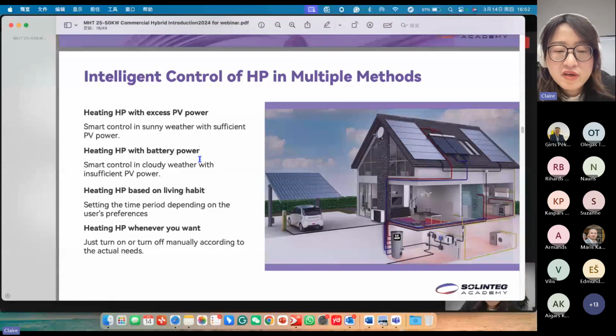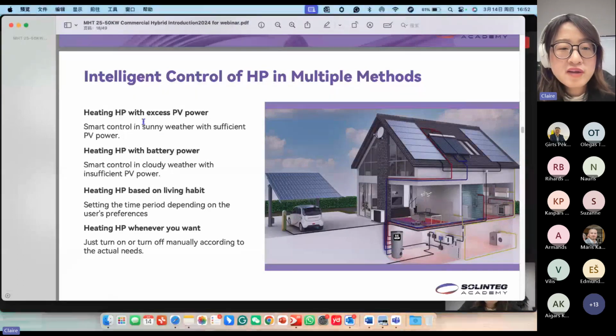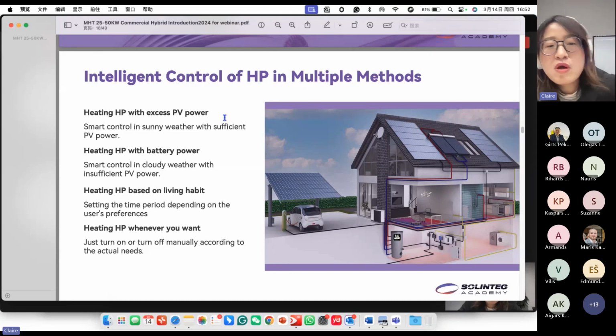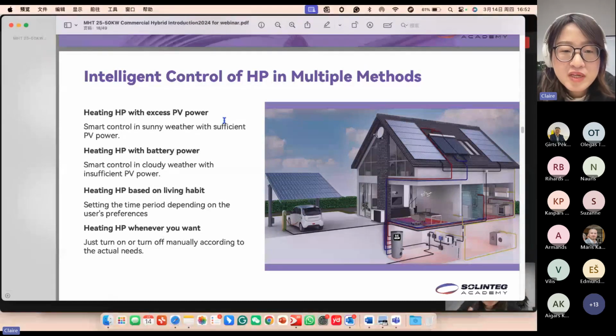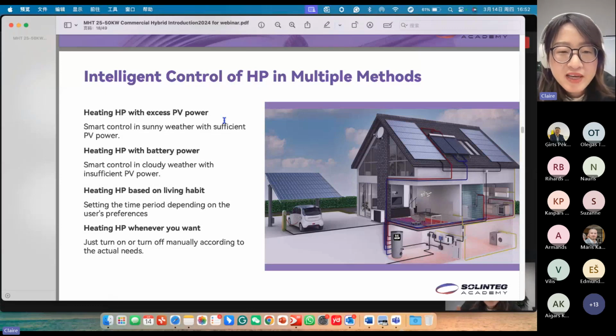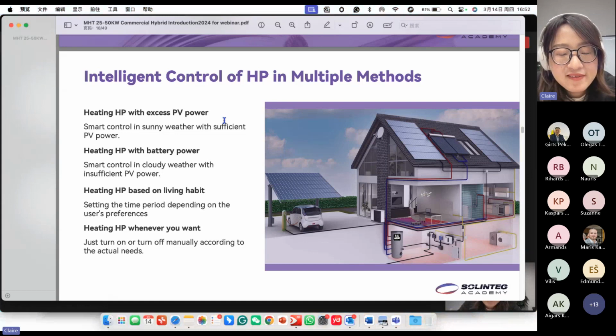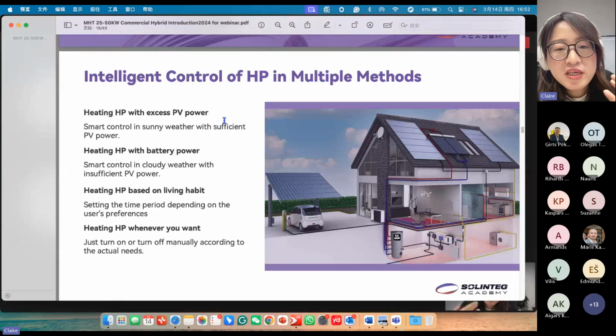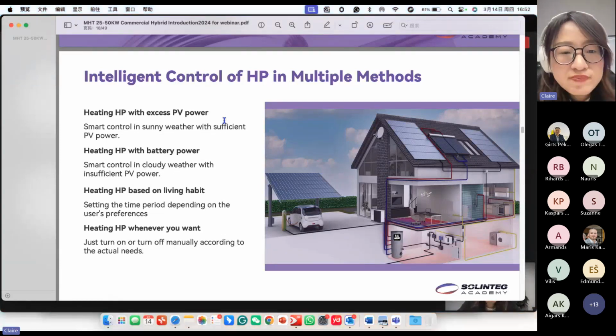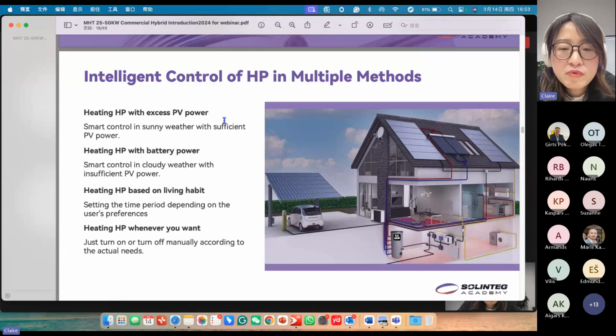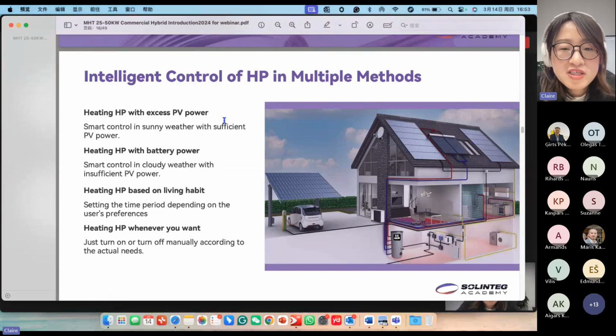We support three ways of controlling the heat pump. The first one is using the excess power to control the heat pump. We can set the threshold for the excess power at which you want to activate the heat pump. For example, if you set 1 kilowatt, when the system detects the power going to the grid is more than 1 kilowatt, the inverter will activate the heat pump to start generating water or start heating the room. And when the power going to the grid is less than 1 kilowatt, according to the value you set, the inverter will stop the heat pump, and then the heat pump will go into the warm preservation mode.